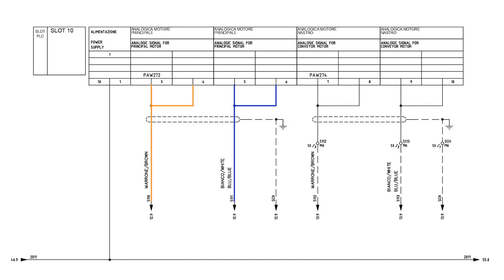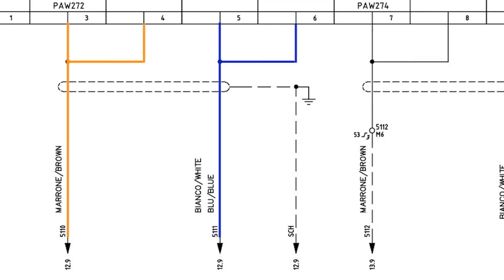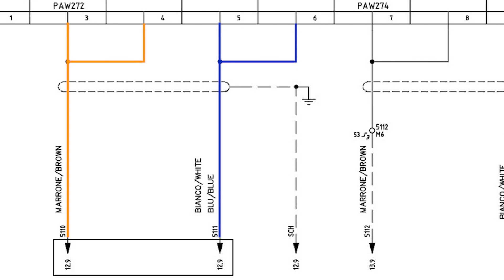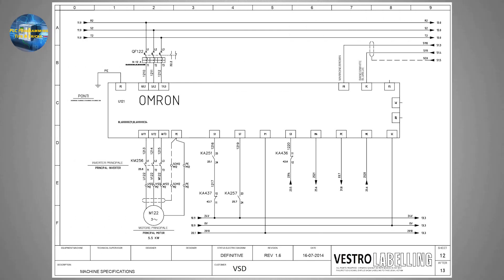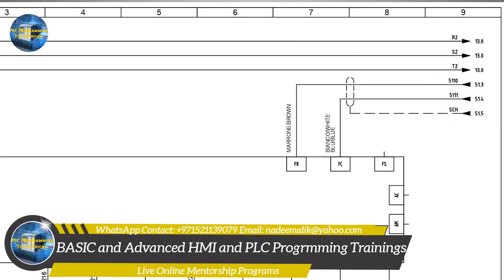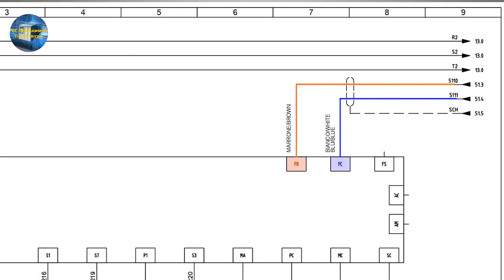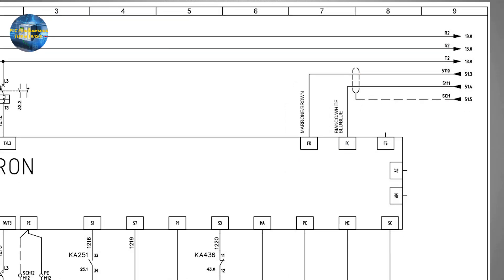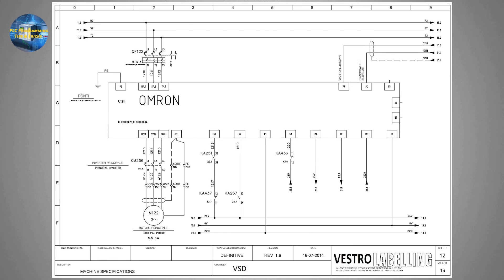On page 51, two wires — brown and blue — come out of the output terminals of this card. The brown wire has the tag '5110' and the blue wire has the tag '5111.' Arrow marks with tag 12.9 indicate we go to sheet number 12, column number 9 to find these wires. The same wires 5110 and 5111 appear on that sheet in column 9 and are connected to the VFD analog input terminals FR and FC. This analog signal is a frequency reference signal to control the motor speed from the PLC.